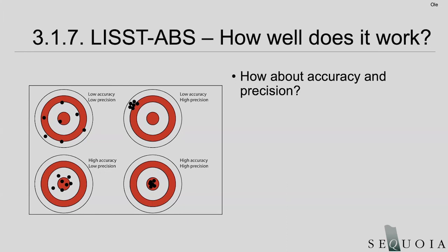If you look at these figures, that explains the difference between accuracy and precision, and look at where the ABS would fall. Then if you start at the bottom right plot with the figure that shows high accuracy and high precision, that's what all sensors and instruments aspire to, hit that bullseye. So you always get as much accuracy and precision as you possibly can get. No sensor is really getting there. This, for example, when you're talking suspended sediment, this would typically be a water sample analyzed by a very experienced laboratory technician who could always get the actual accuracy and precision.